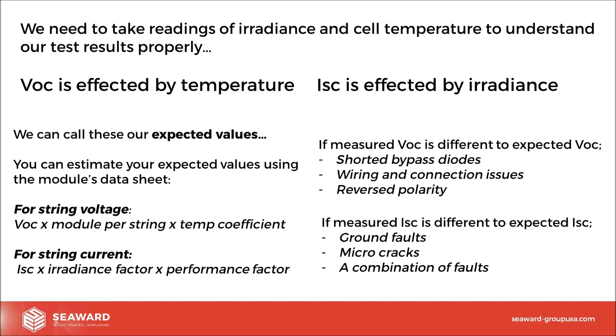Similarly with current, we can take the ISC of the back of the panel, and that will be at 1000 watts per meter squared, and we can also add in a performance factor. Now, if we're just using a clamp meter, we get operational current, we have no idea how the irradiance is affecting its output. So therefore, we can't get an accurate expected value. So our measured value has no context, and it's almost rendered meaningless. So really, by using traditional tools, we're not getting all of the information we require. We need those environmental conditions tested and verified at the point of test of voltage and of current.